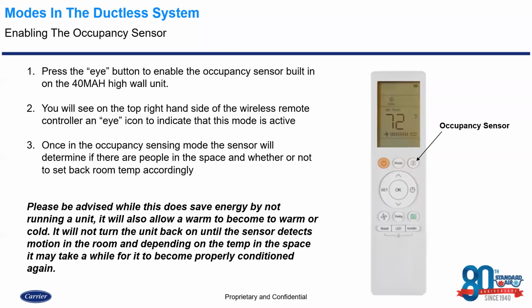Once in the occupancy sensing mode, the sensor will determine if there are people in the space and whether or not to set back the room temp accordingly. Okay, and it is important to note with the occupancy sensing mode, while it is a really great feature and it sounds wonderful, if the customer has this in a bedroom and they put it on an occupancy sensing mode, when they lay down for the evening and their movement is at a minimum and the unit does not detect movement in the space, it's going to set back the temperature in the room itself, which could create warm or cold conditions depending on the time of the year. So it's certainly something that you want to advise the customer of. While it is a great feature and it's marketed very well, this mode is not going to be for everybody.